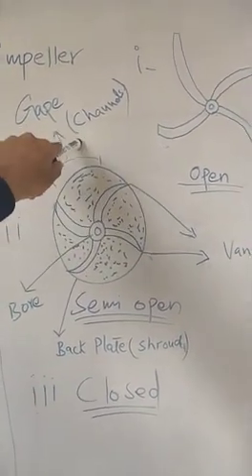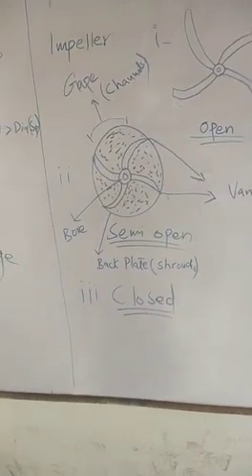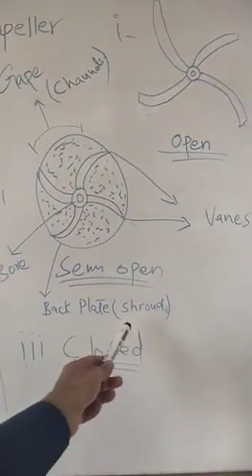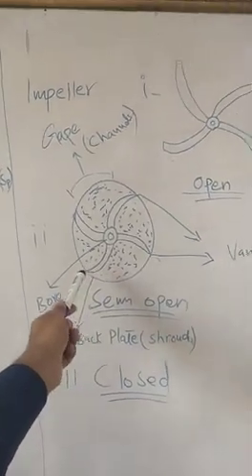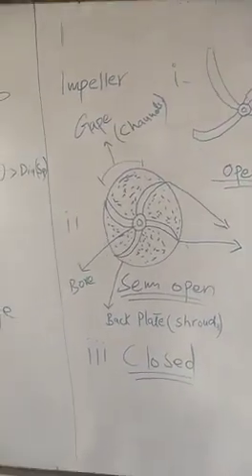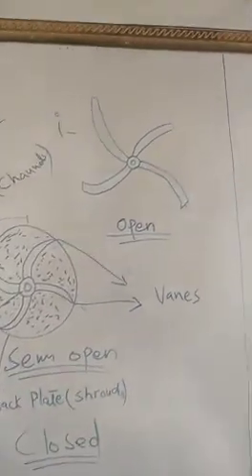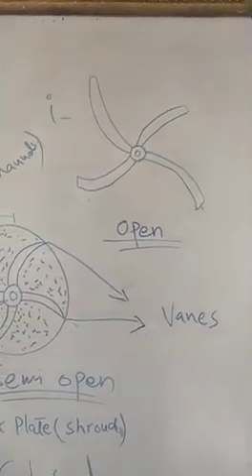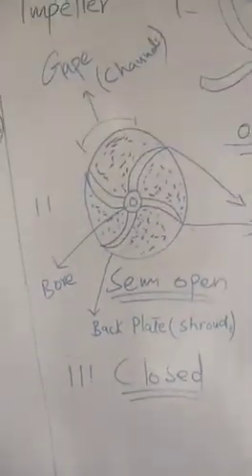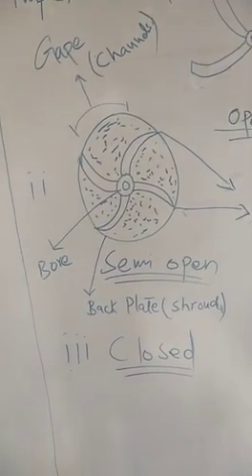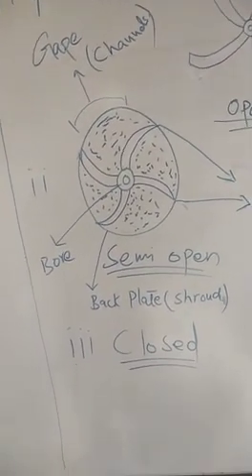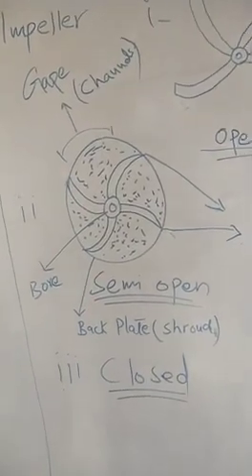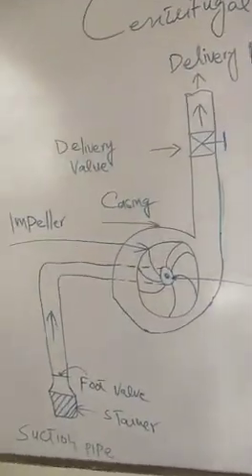The gap between the vanes is called channels. The plate on which the blades (vanes) are mounted is called a shroud. In a semi-open impeller, there is one plate at the back, called the shroud. In an open impeller, there is no shroud — only vanes and the bore. In a closed impeller, there are two shrouds, i.e., two plates, with the vanes positioned between them, making the vanes not visible from outside.